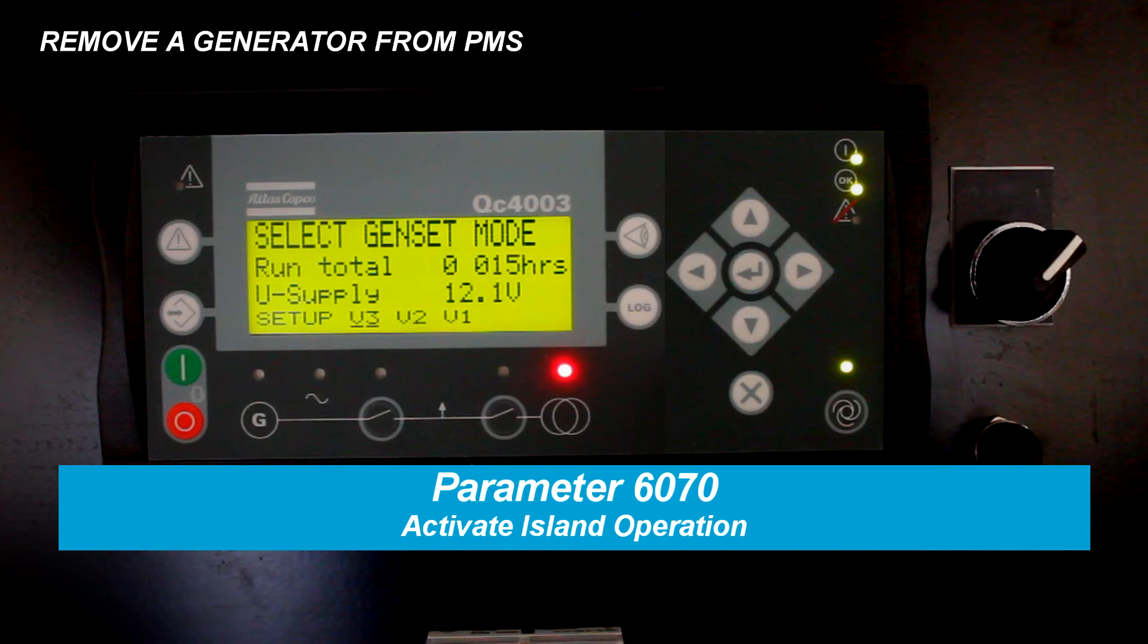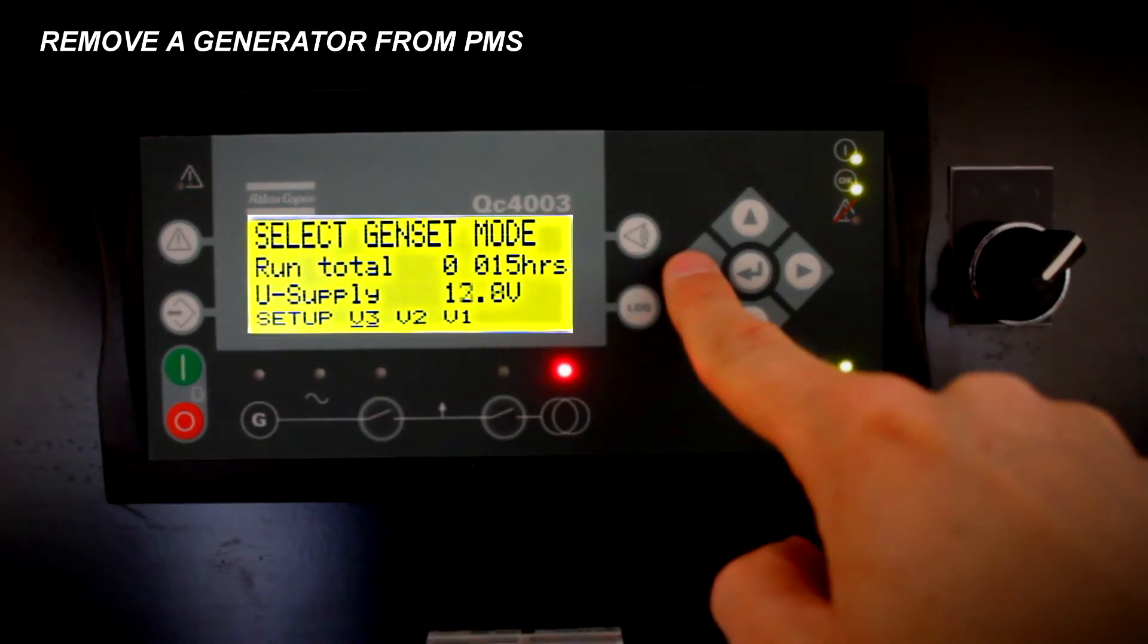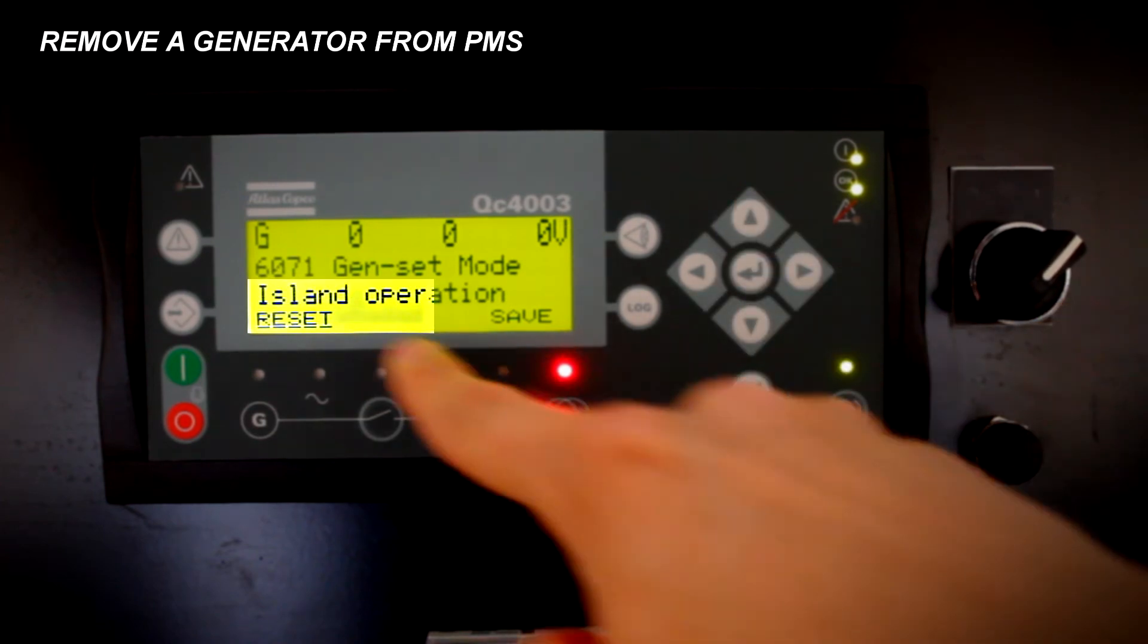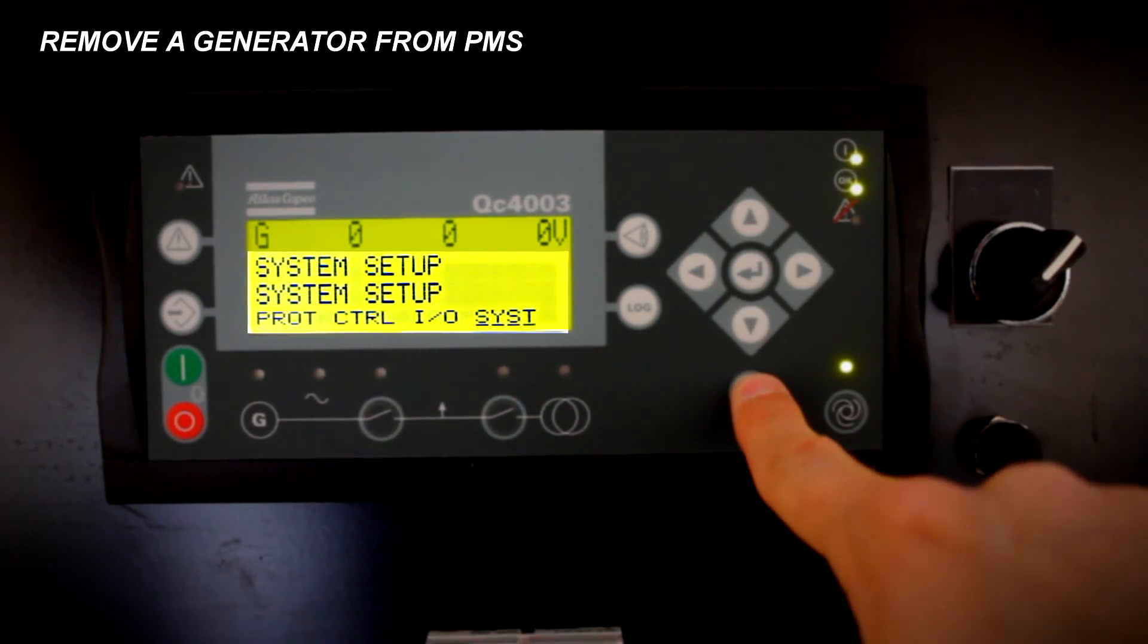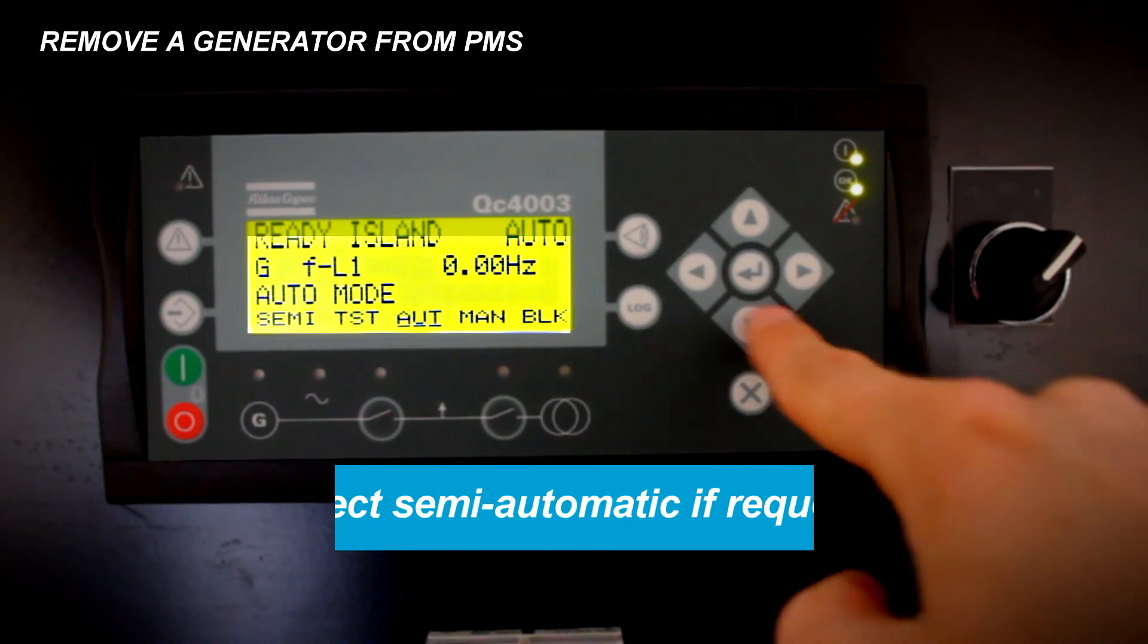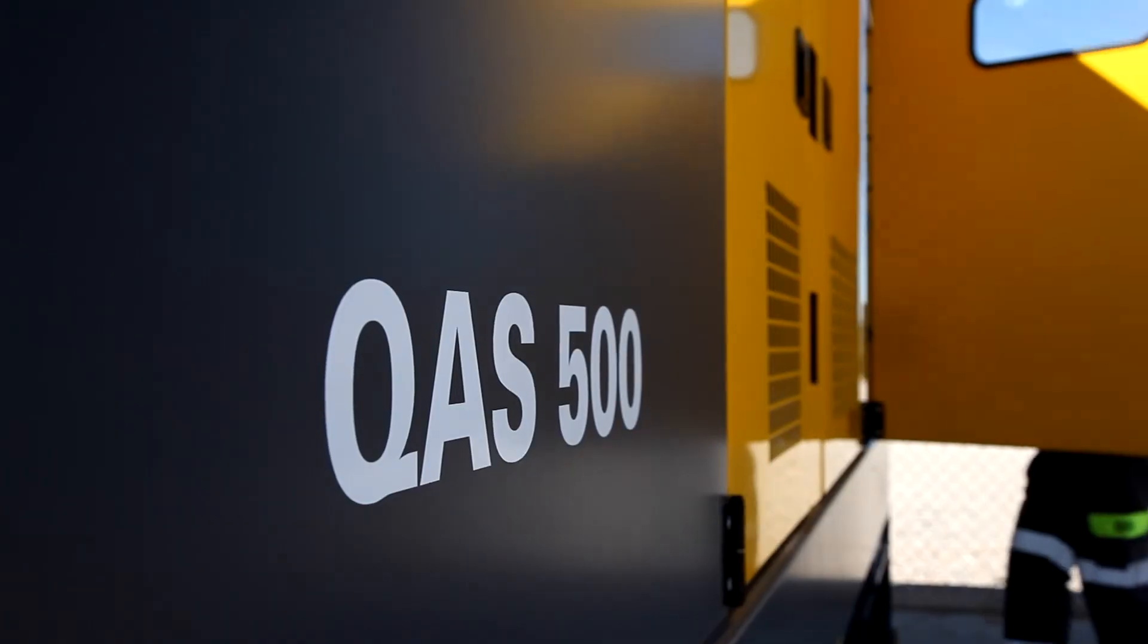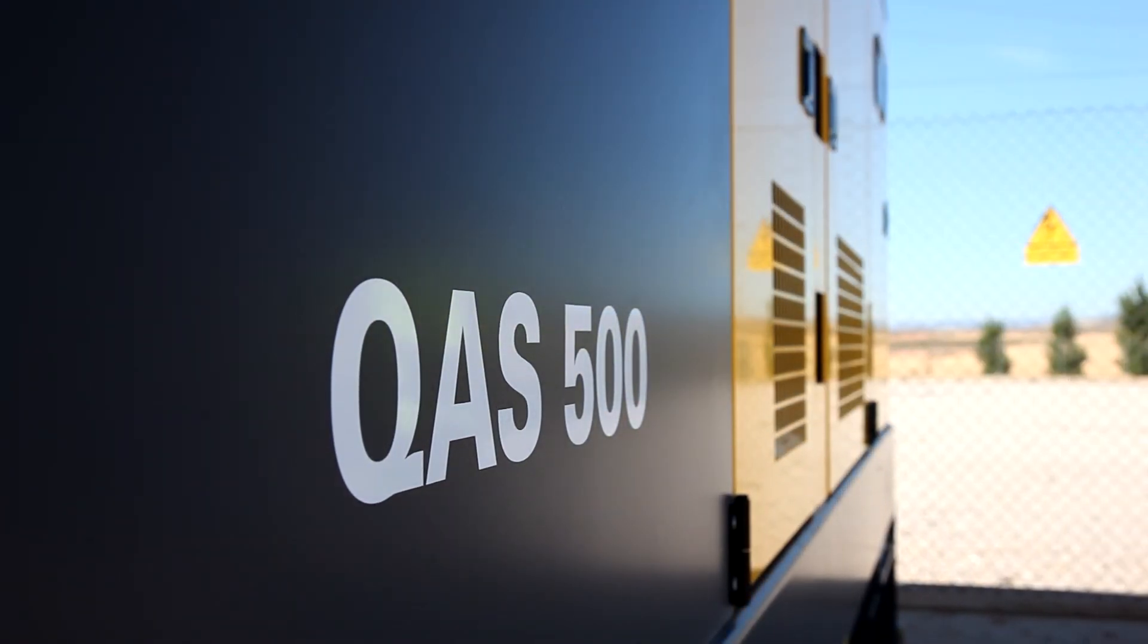Just go through the menu: setup, system, general. Scroll until you find parameter 6070. Enter the customer password if required. Now the unit is no longer connected with the other generators and is ready to operate in island mode.